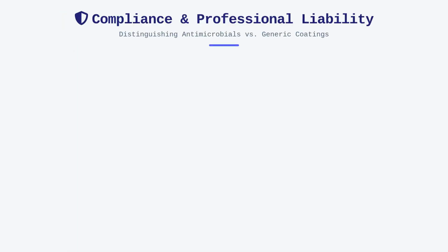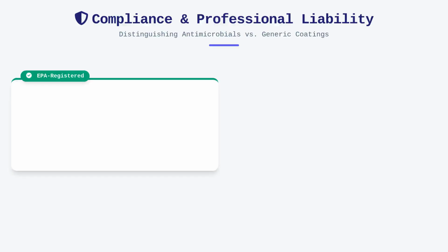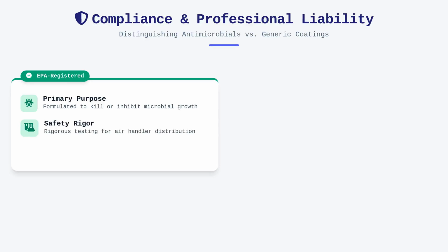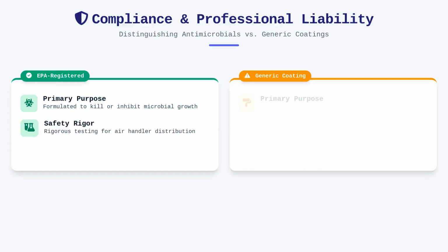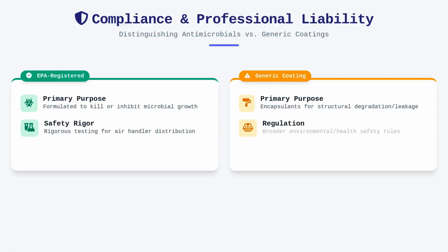Distinguishing between an EPA-registered antimicrobial and a generic coating or sealant is critical for your professional liability. An antimicrobial pesticide is formulated to kill or inhibit microbial growth, and it undergoes rigorous testing to assess its safety when circulated through an air handler or distribution network. Coatings, conversely, are often categorized as encapsulants intended to address structural degradation or air leakage. And while they may contain antimicrobial additives, they are typically regulated differently under broader environmental and health safety rules.